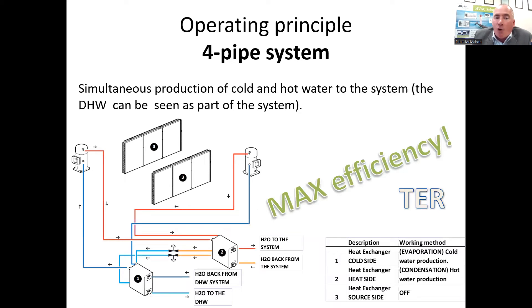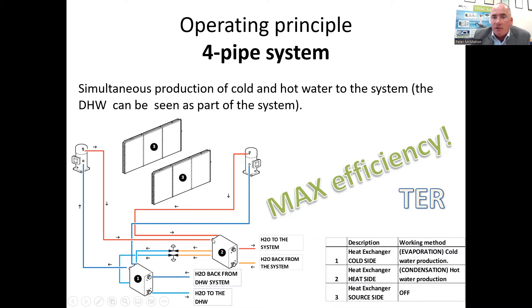Or of course when you have simultaneous cooling and heating at the same time, you can see the outer coils — what would be the condenser or evaporator — those outer air coils are not being used. In this mode of operation you're basically doubling your efficiency, because you're getting space heating and space cooling, basically chilled water and warm water, at the same time. You have a total efficiency ratio which is typically more than double your energy efficiency ratio, so it's a very efficient method of generating your space heating and space cooling simultaneously — you're getting one for free, so to speak.